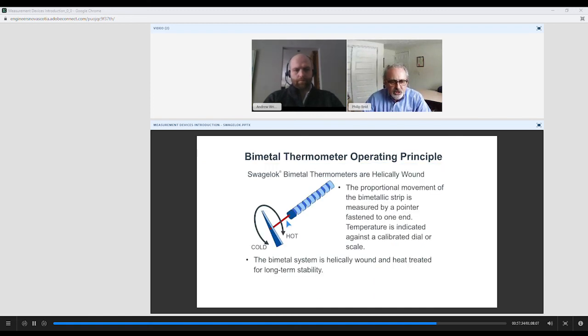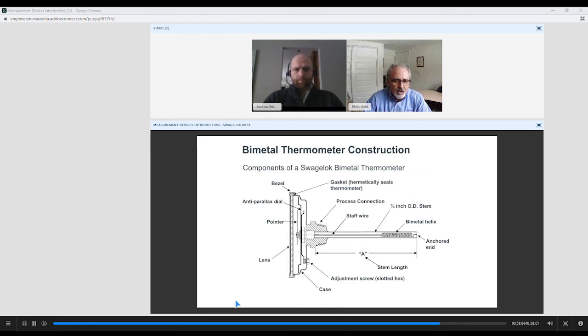And so as it starts to expand or contract, it will start to twist on this helical wound bimetal strip in the thermometer, and we'll see where this is in just a second. The proportional movement of the bimetal strip is measured by the pointer out in the face, and the temperature is indicated on a calibrated dial scale. The bimetal system is helically wound and heat treated for very stable, long-term life. So here's what it looks like if we were to do a cutaway cross-section.